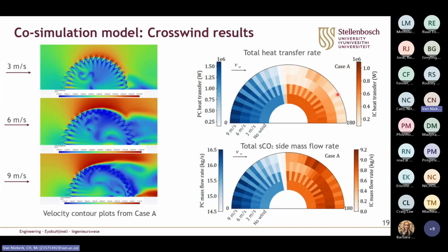We do see an interesting effect though. Here at the back, we have some performance recovery for the 6 meter per second crosswind, which is effectively due to the flow that starts to separate from these rear tube banks, forming a low velocity zone and then increases the local pressure in that zone. That then allows the tower to re-entrain some air across those tube banks, allowing for the small performance recovery that we see. It is interesting to see that this effect is not sustained for the 9 meters per second case, but it's explained by this very large rotating vortex structure that impedes any formation of high pressure zones at the outside of the cooling tower.